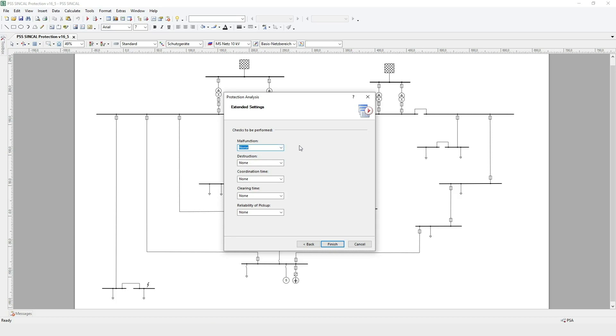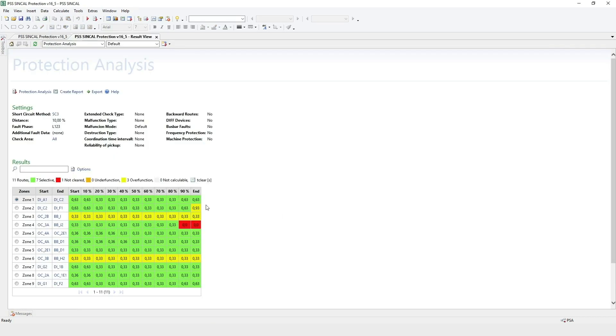First, we'll perform a protection analysis with only the base settings. The result matrix shows we have two not cleared fault locations, which are red, and some over-functions or unwanted operations of protection devices, which are yellow. The fault clearing time for every fault location is also displayed in the cell.